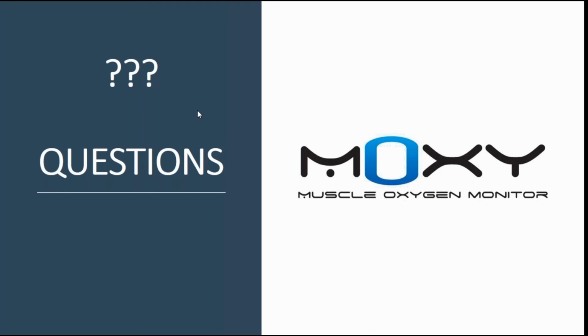So when I went through how the Moxy works and some of those design features, I think all 4 of them, with the data I have now, and I don't know for sure, since I haven't tested the ones that are in development, I think they will all have similar issues to what we showed in the demonstration, where, at least in some cases, they won't be able to measure with useful accuracy on that scale of 0 to 100. So if you do an occlusion and we expect to see a 0 and they're showing a 60, it's hard to know that 60 is really a low number. That's where things can get confusing.